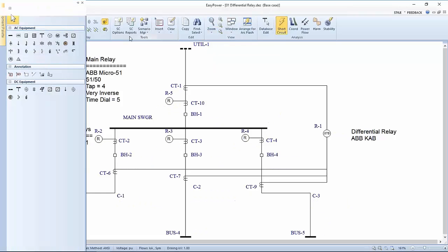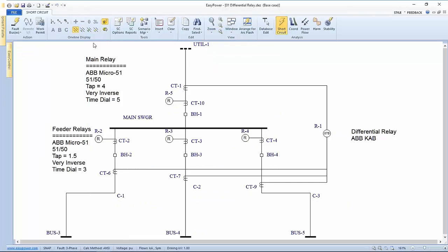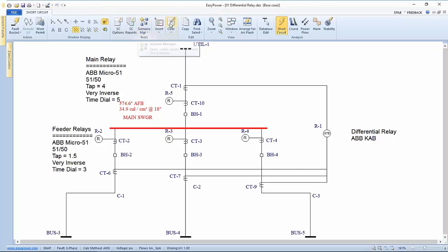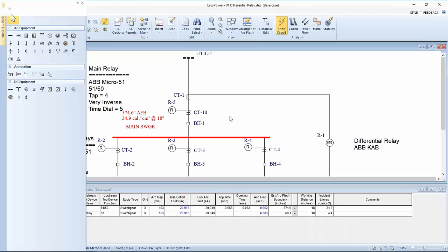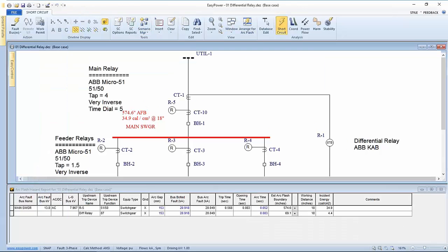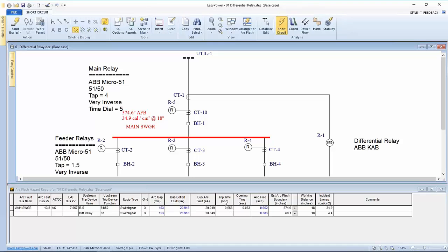At that point, we know there's something wrong between these two sets of CTs. So we can't go any further as far as opening up breakers downstream of this particular device. Now what this allows us is the ability when we go into the short circuit focus, and let's fault this bus specifically, and we look at our arc flash. We see that normally if we have a phase over current, then that trip time has been set and the incident energy was what we show at 34.9 calories. On the other hand, if the differential relay is the tripping device, and we see here that the trip time is going to be the 83 milliseconds that we input, and so our incident energy will be 4.4 calories.